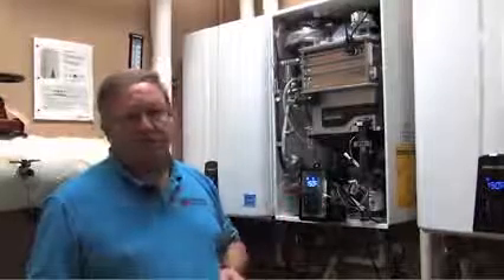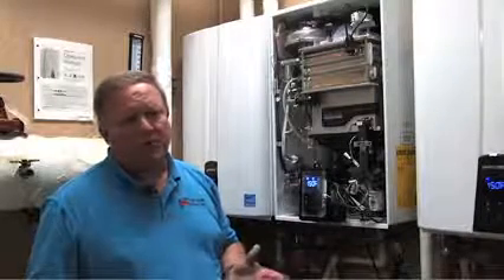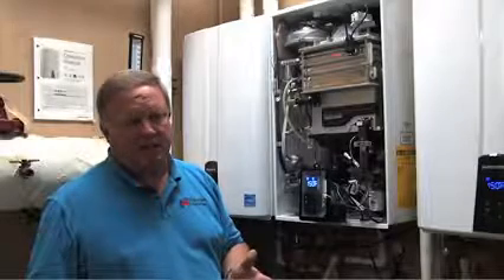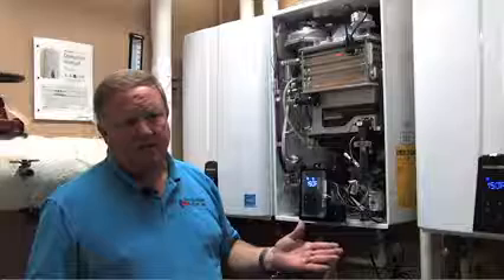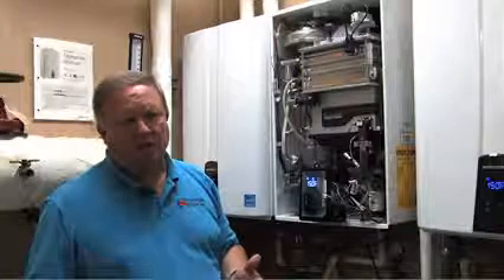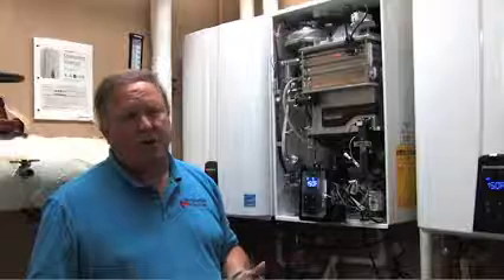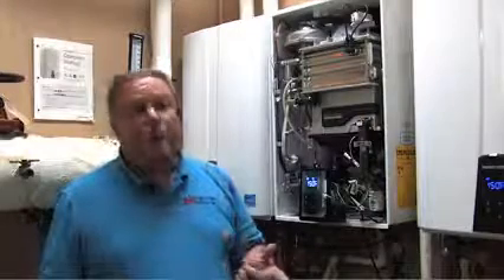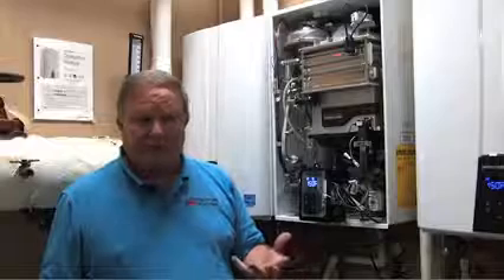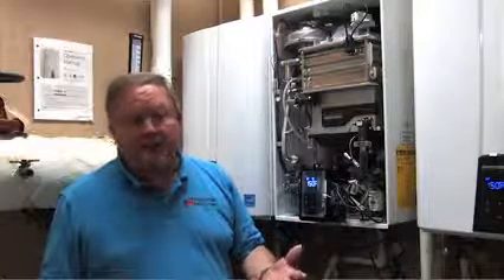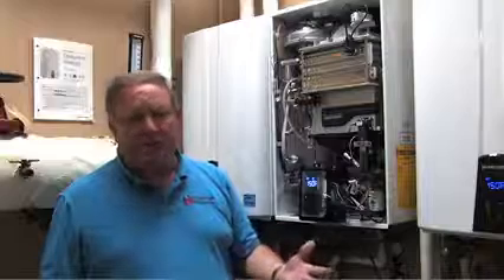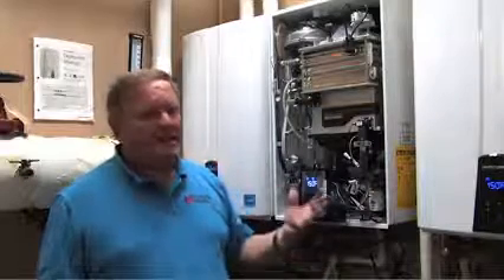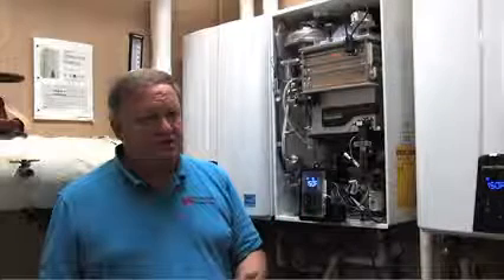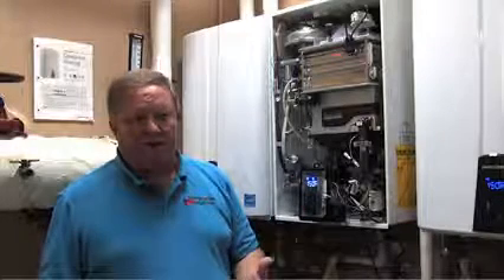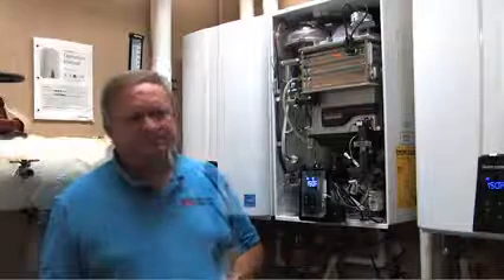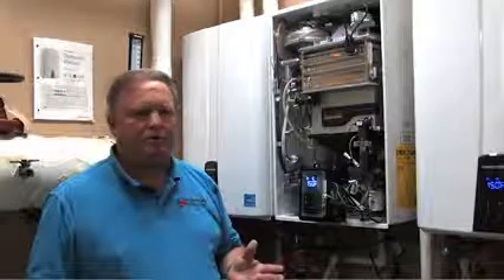These can be lower temperatures because they're much more efficient. Most of your tankless are in the 83 to 85% efficient. These are in excess of 95%. So we're much more efficient, we use less fuel, and we burn what fuel we do use much more efficiently. The advantage of 2 heat exchangers is that with the first heat exchanger, we get somewhere around 80 to 85% of our efficiency, very similar to other manufacturers with single heat exchangers. The second heat exchanger actually allows us to pick up more efficiency and get closer to the 95%, which these are capable of.